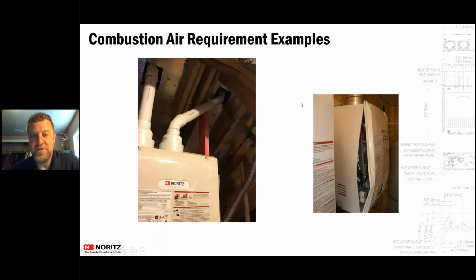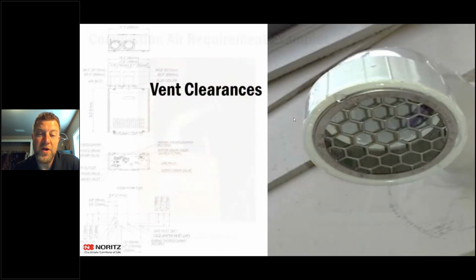Here's a couple of examples of bad combustion air. This first one, this unit here, is an older unit that requires that you run it in 3-inch PVC, and they bailed it down and went with 2-inch PVC. So this install would be great if that was 3-inch PVC, but it doesn't have enough combustion air coming in, so it's probably throwing a 90 code. This unit next to it, they blocked the air intake and the exhaust, so it made a bit of a bang inside of that unit and deformed that unit, which is never ever good. So make sure that you have it vented 100% correctly.